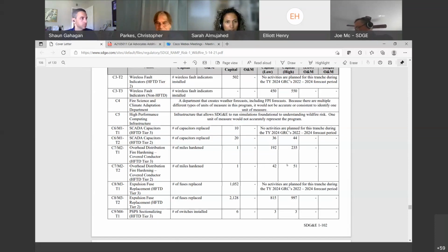We're definitely studying it as we go, and there hasn't been enough data yet to make any major conclusions. But some of the things we're learning include, for example, how many steel poles can be reutilized so we don't have to replace them. We don't have exact numbers, but that's the type of thing we're gathering as we implement covered conductor. Some areas require larger size wire, and the cost increases could lead us to revisit whether it makes sense to apply covered conductor or switch to underground, since the sizing ends up bigger, costing more, and requiring intercept poles. So we're learning a lot as we implement.